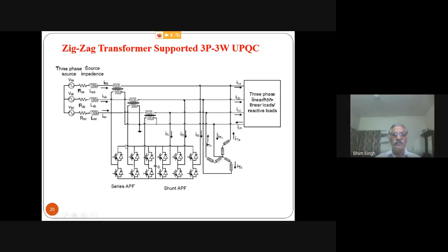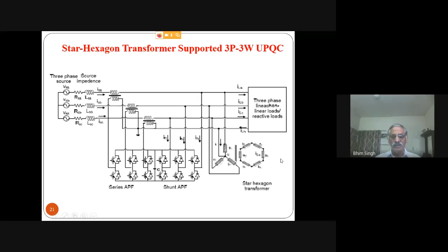But still the converter you can have with even just 3 legs also. So there are many possibilities, like neutral current compensation can come with the help of any closed winding you have, either zigzag or a closed winding. The closed winding can be a hexagon, polygon, or your delta connection. Okay, all these can give a closed path along with this star connection, or you must have a zigzag connection where triplen harmonics get compensated. So either hexagon or polygon, which I told, or you can use the Scott connection or T connection. That also compensates for your neutral current along with the zigzag.